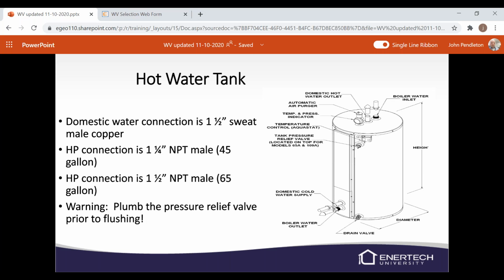the 65-gallon. There is a pressure relief, so if you flush it, plumb it to a drain. That's probably what I would do, because if you get above, I think it's 30 or 35 PSI, then it's going to pop open that relief. And it does happen. It's not a huge problem. You will drop some water in your flow center or your flush cart tank because you're going to discharge a little bit of water, but try to keep the pressure down so you don't. So try not to deadhead your pump on your flush cart when you're flushing the tank, or else you will definitely open that relief. Not a big deal as long as you've got it piped to a drain.